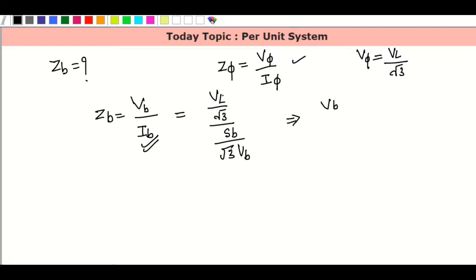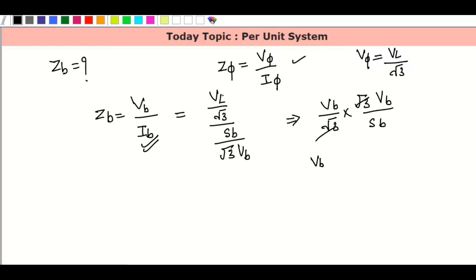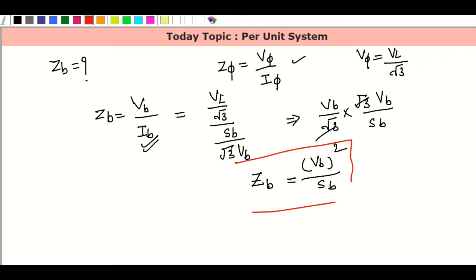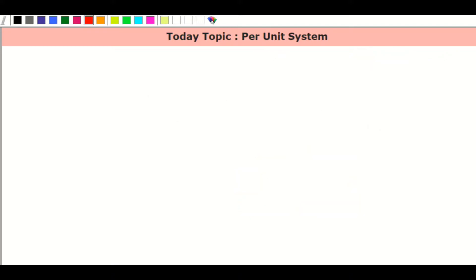So this one and this one cancel. V base squared divided by S base — same as single phase. This is the base impedance formula. So the three-phase and single phase per unit values have the same Z base formula: V base squared divided by S base.